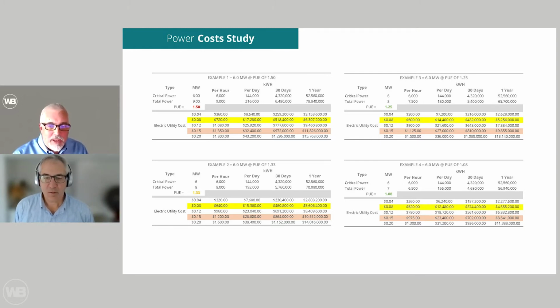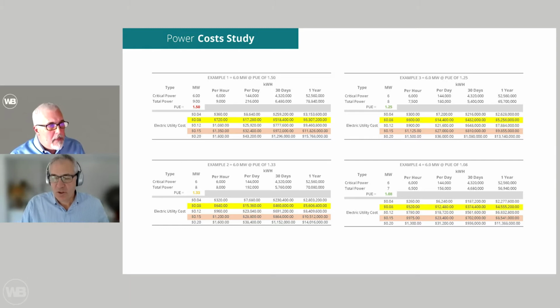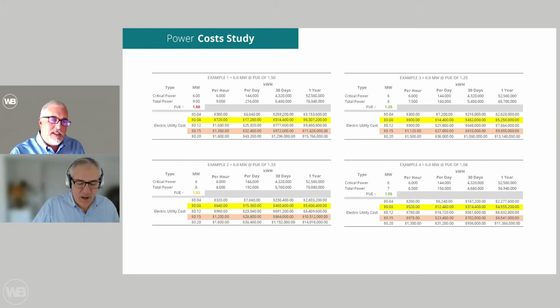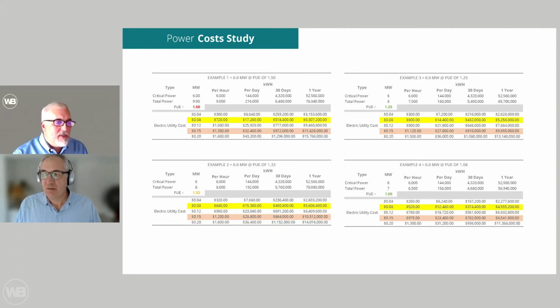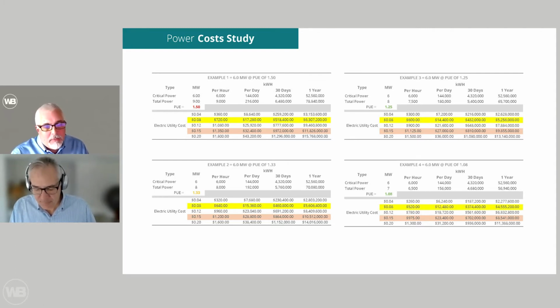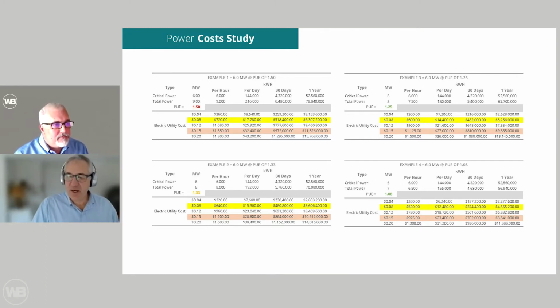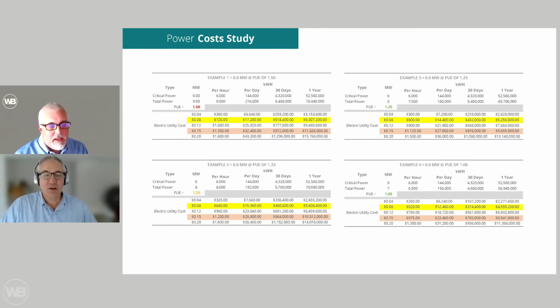In the last example, example 4, we're only using an extra megawatt, which is a 1.08, very aggressive. We've seen a couple of users get to that point, but typically you have to have some sort of free cooling or something to get most of the HVAC out of the building to do that. A 6 megawatt generator, how many square feet is that roughly? Well it depends, everybody's critically different, but it's around 30,000 square feet, maybe up to 40. So for a 30,000 square foot data center, the electric utility costs can vary between 11.3 million to 15.7 million.